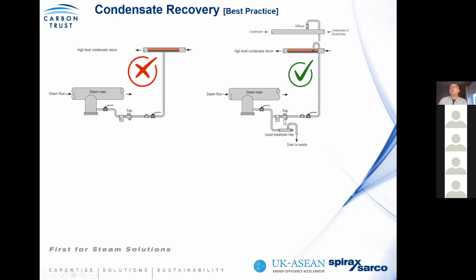Where you have certain mains distribution traps, for example a thermodynamic trap, which has a blast function, you should have a diffuser installed where it interconnects to the steam distribution system. The reason for the diffuser is to basically reduce the kinetic shock to the condensate system when you're discharging condensate and steam at high velocity.